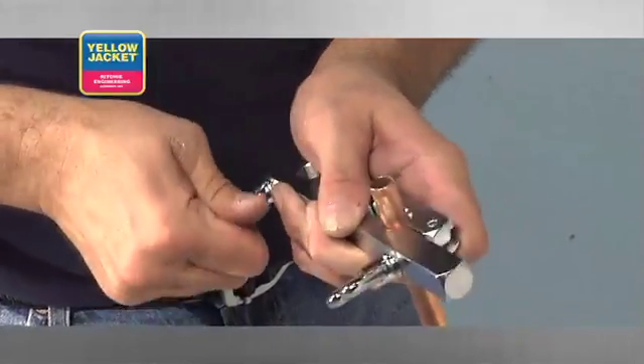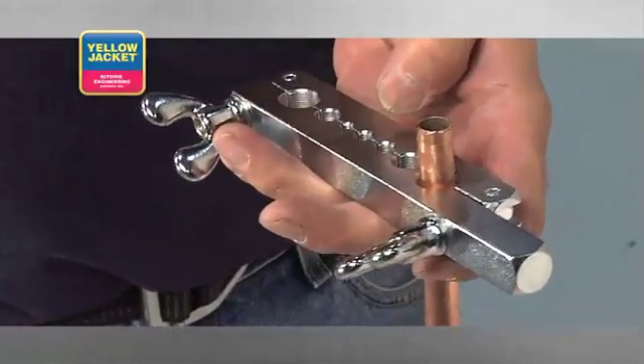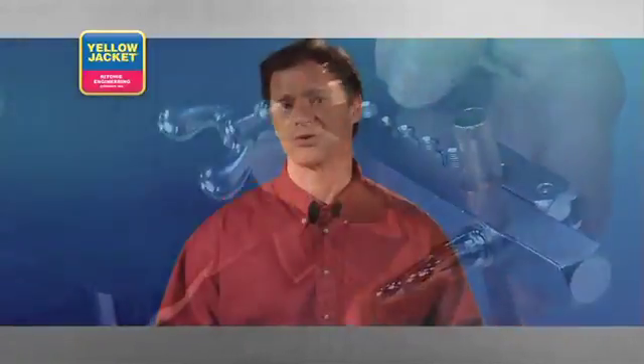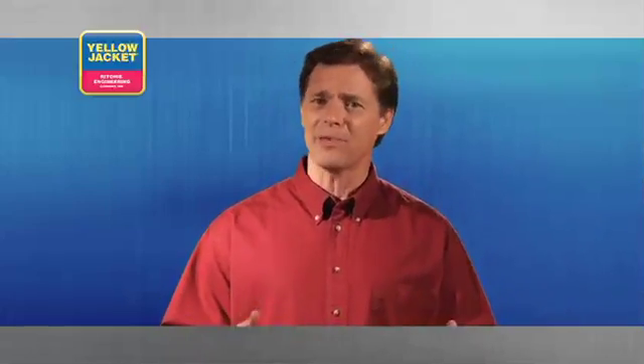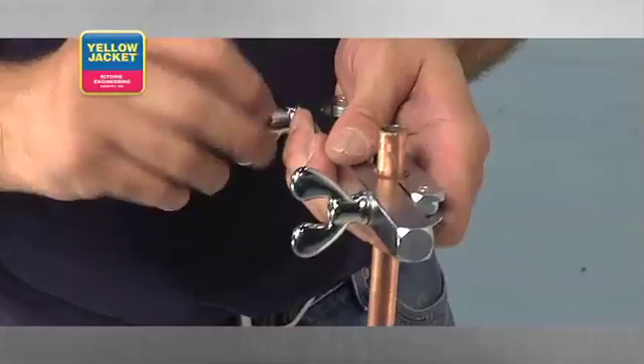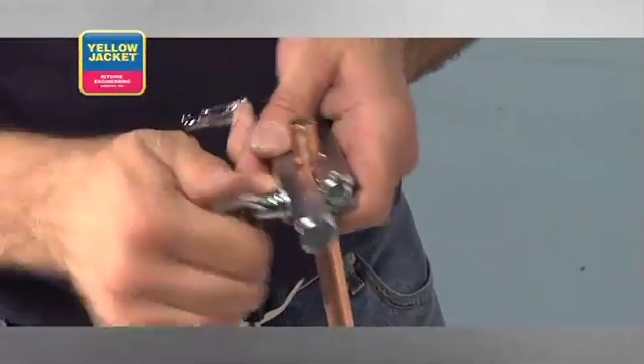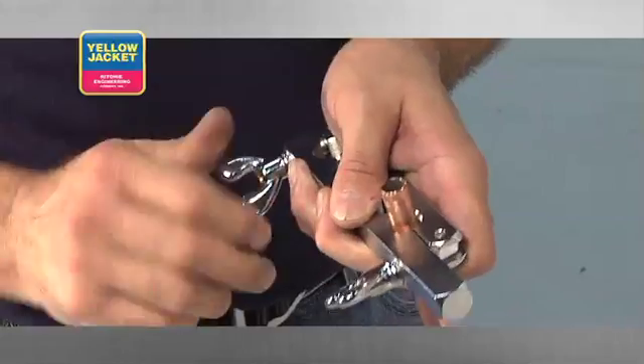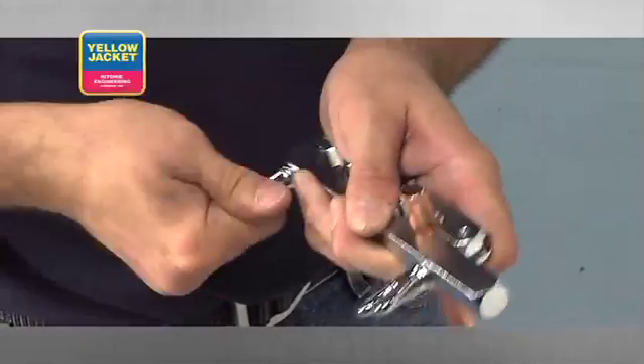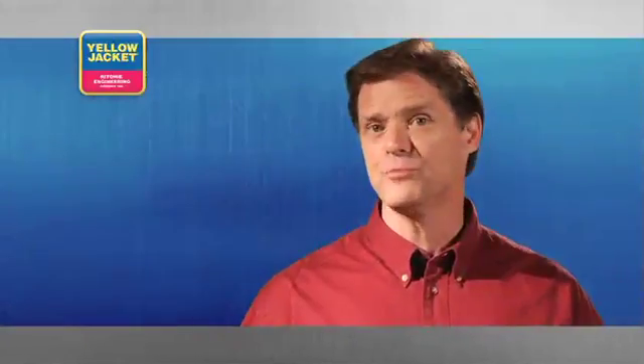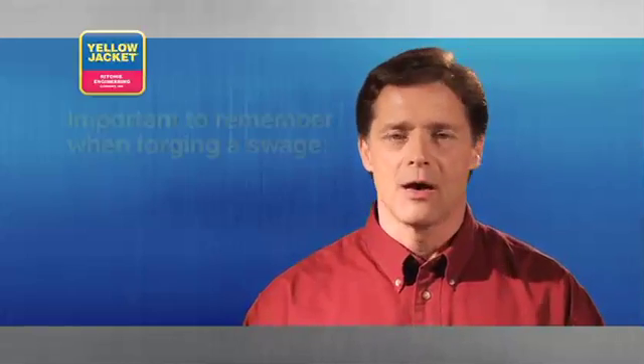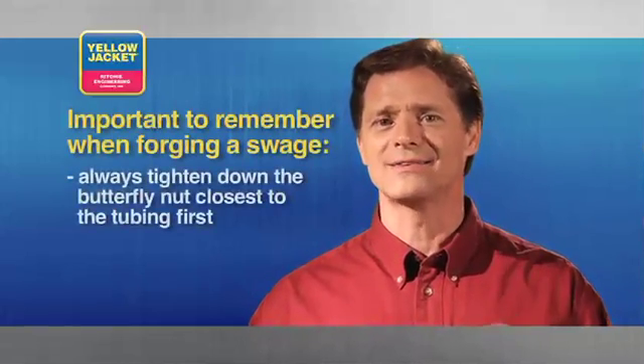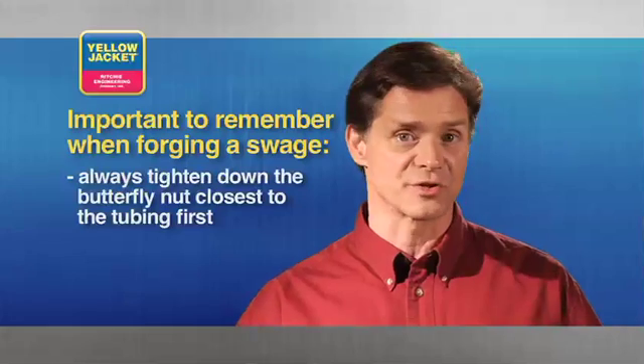Tightening the butterfly nuts for a swage is a little more critical due to the amount of force required to forge a swage. So after tightening down the second nut, it might be helpful to back it off a bit, and go back to the first nut and tighten it a bit more. Return back to the second nut again, and tighten it down. If the tube slides during the swaging process, repeat this back and forth tightening to improve the grip on the tubing. But remember, always tighten down the butterfly nut closest to the tubing first.